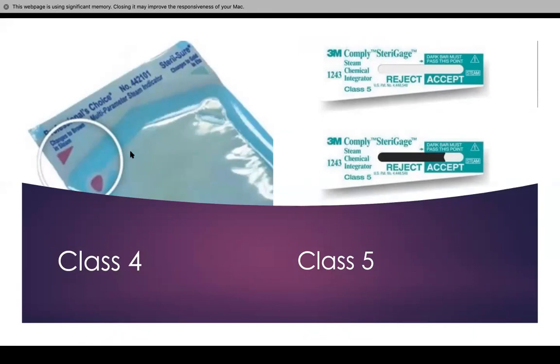These ones have to have a color change. As you can see, it clearly says it on the class 5 chemical indicators — if the darkness, if a gray or black point has passed this marker, that means you are allowed to use it. If it has not, then you cannot use it and you have to recall everything.